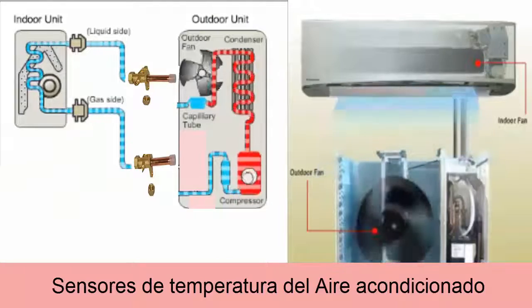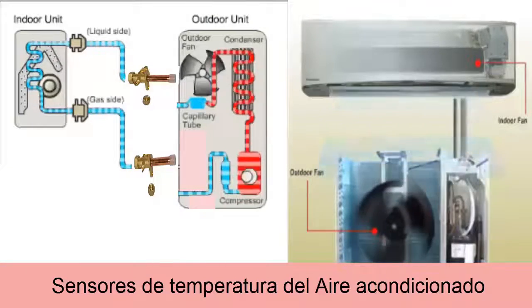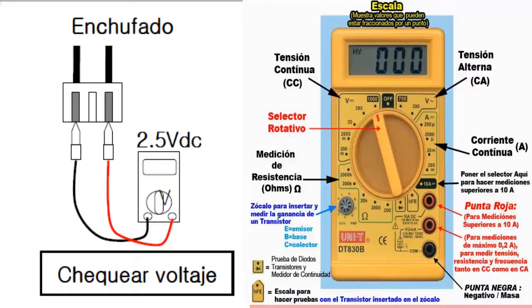It is also important to verify the power supply of the card to the sensor, since the card must supply a voltage so that the sensor can work. With the sensor connected, we verify the voltage using tips or needles with a multimeter on the scale of 20 volts DC. The value we are going to read is about 2.5 volts.